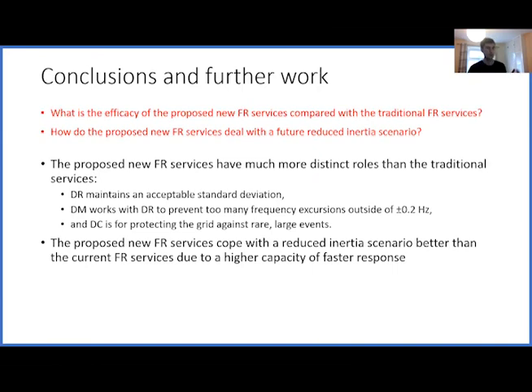To conclude, with my research questions at the top again, I'd say the new FR services have a much more distinct role than the traditional services. Dynamic regulation maintains an acceptable standard deviation. Moderation works with regulation to prevent too many frequency excursions outside of 0.2 hertz. Dynamic containment, which is actually online at the moment and started in October, is for protecting the grid against rare but large frequency events. All three together, with their capacities combined, really determine how you can manage your frequency when there's a large in-feed loss.